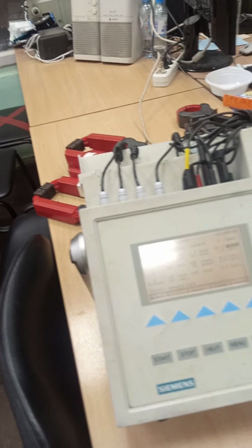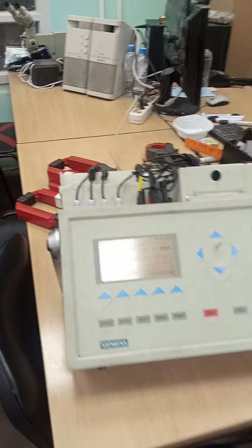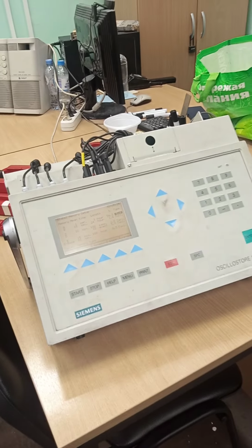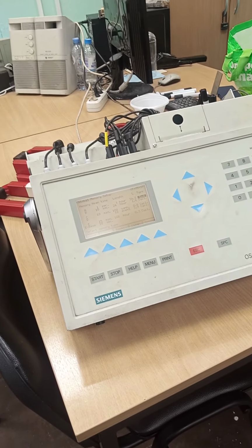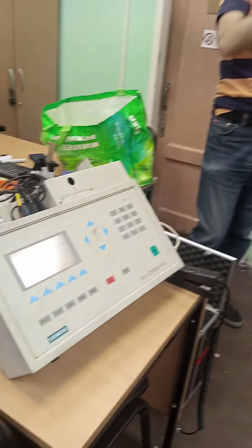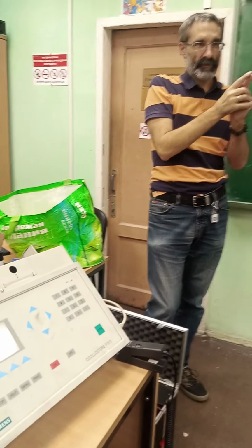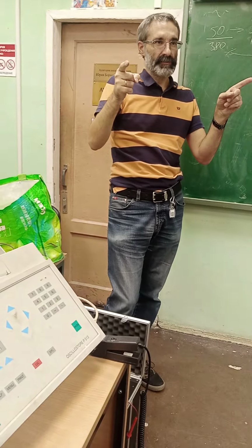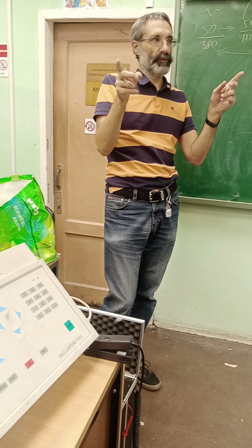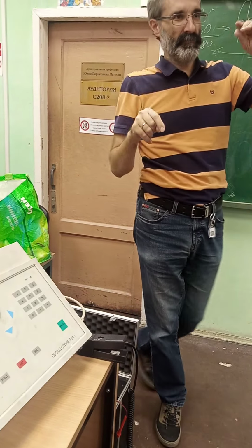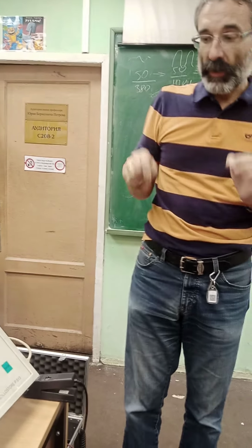So if we will measure every minute, for example, we will not see it on the diagram, because even if this impulse is high, but one impulse during 1 period, averaged at 10 minutes, will not be seen on the diagram. It will be very low. Average value will be almost normal. So we need to perform measurement in this case with maximum precision.